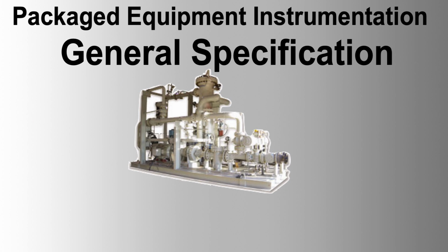Tubes and fittings should be a minimum of half-inch with 0.049-inch wall thickness, using double compression flareless type fittings from approved manufacturers. Installation of instrument tubing: impulse lines should be as short as possible and preferably in the vertical plane. The slope should be 10 mm per 200 mm length, with supports and trays arranged neatly for self-draining and minimal dirt collection. Welding supports to process piping or vessels is not permissible.